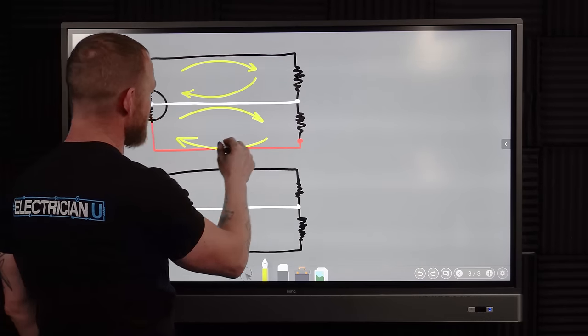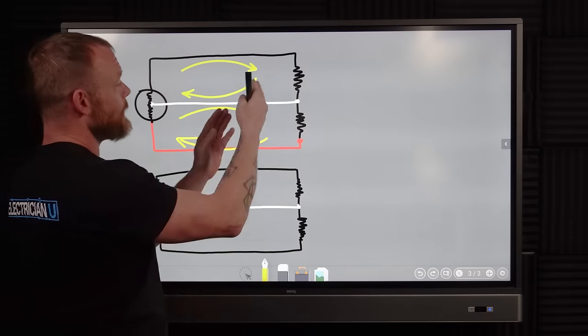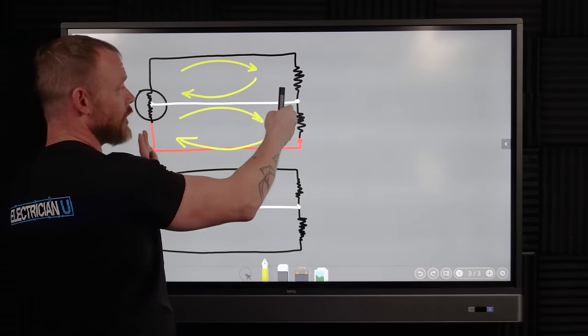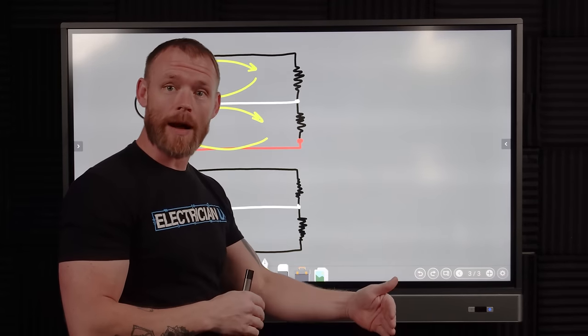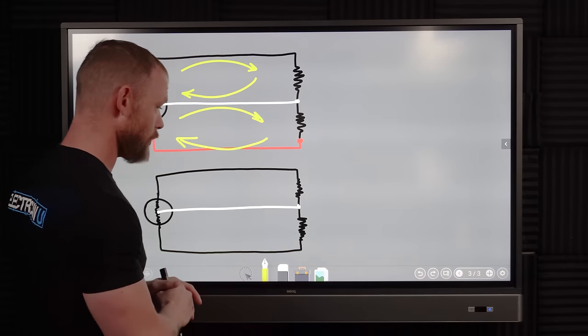The only other way current has through the circuit to make that completed loop is through the 240 volts. What that does is instead of just having one load in a 120-volt circuit, it takes two loads of equal size and puts them in series in a 240-volt circuit — which still allows them to operate at the exact same level as if there were only one of them at the 120-volt level.